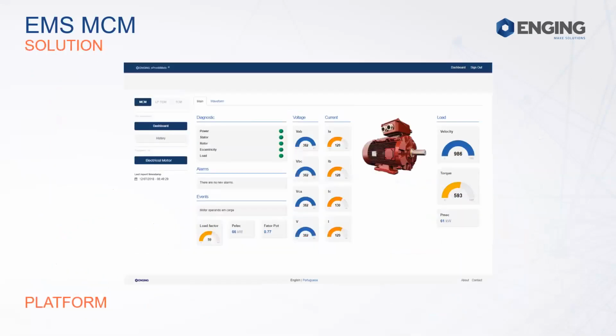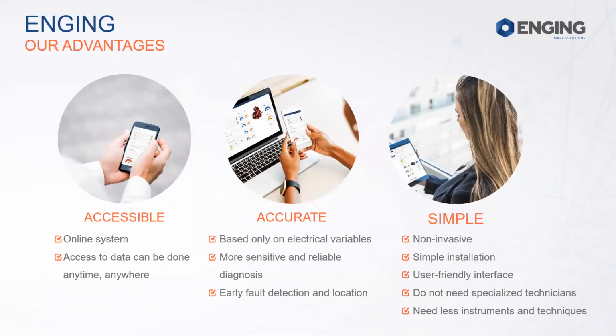So these are the main faults we detect: rotor, bearings, and stator. This is the layout of the software. You have the five main diagnostic alerts: power, stator, rotor, eccentricity, and load. This changes color if we reach a fault or no detection. You also have the load factor, voltage and current measurements, load capacity, velocity, and torque of the motor. Basically, we are able to monitor the whole part of a motor.